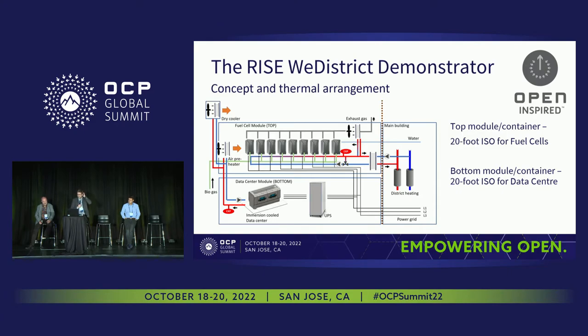This is a more detailed sketch of what's going on inside. In principle, the bottom container has the immersion system, which rejects heat up to the top container containing the fuel cell. There's an air preheater that warms the intake air, since the fuel cells don't like very cold air, which could be minus 25 degrees during winter. The heat coming out of the fuel cell is rejected through a heat exchanger to the district heating system, shown to the right of the picture.